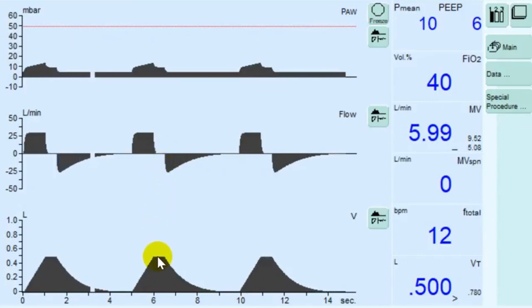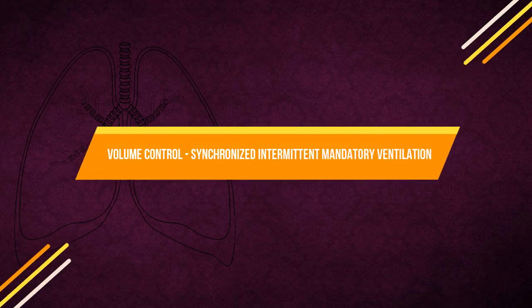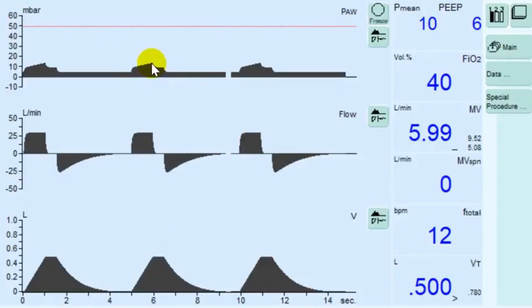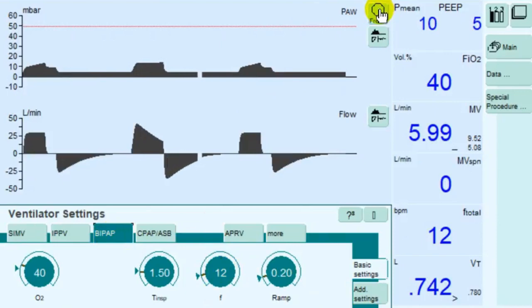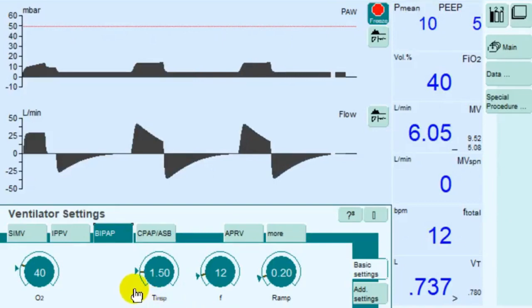The next mode is Volume Control Synchronized Intermittent Mandatory Ventilation. The patient is supplied with the set tidal volume during mandatory breaths, which are synchronized with the patient's own breathing attempts. To prevent a mandatory breath from being applied during spontaneous expiration, a patient-triggered mandatory breath can only be triggered within a trigger window. If the expiration phase and spontaneous breathing time is shortened due to synchronization, the next expiration phase will be extended, preventing a change in the number of mandatory breaths.